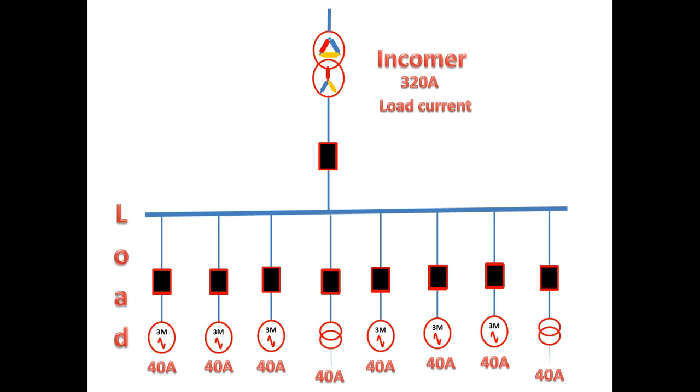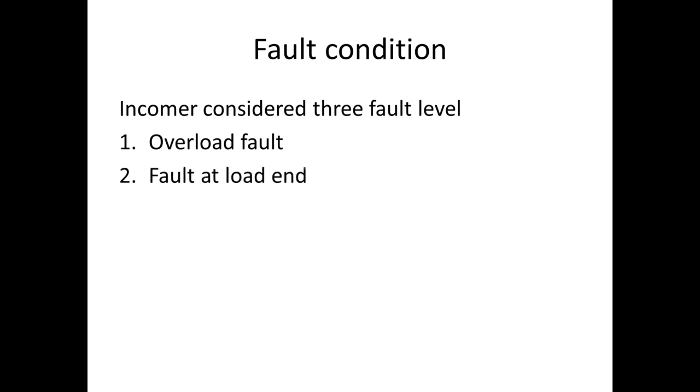The feeder load current is 40A and the full load current for the incomer is 320A. For the incomer alone we can consider three fault levels: first, overload fault; second, fault at load end; third, fault nearer to the incomer.